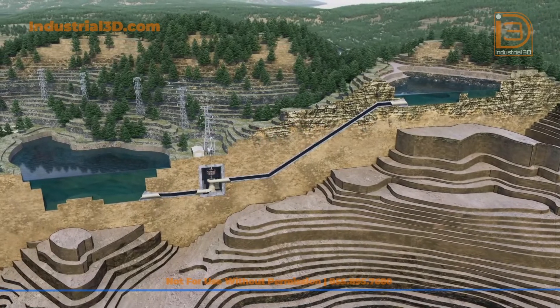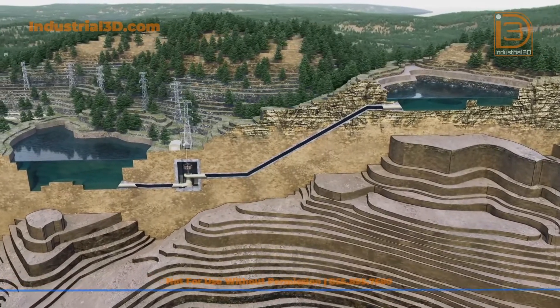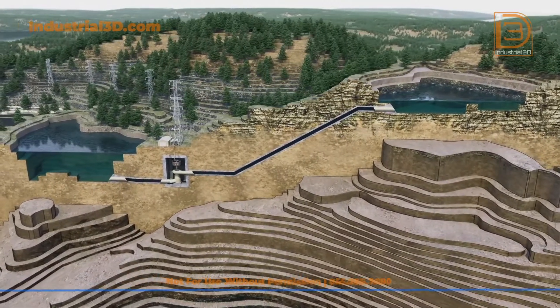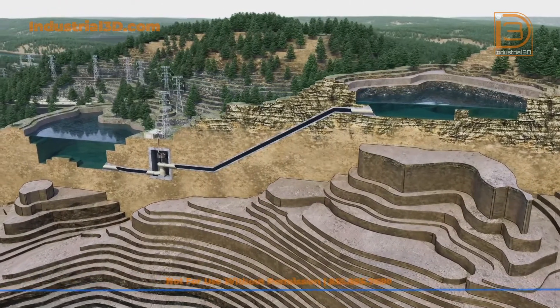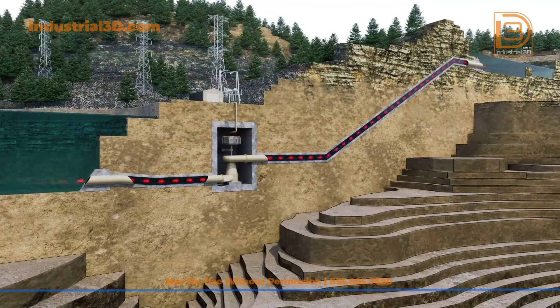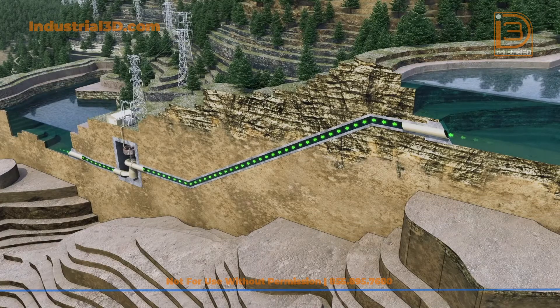The backbone of America's energy storage is pumped storage hydroelectric — it is 94% of actual energy storage. Pumped hydroelectric stores 10 to 20 hours of energy, compared with batteries, which store 1 to 4 hours. Pumped storage works by pumping water uphill to store electricity when excess electricity is available, and allowing it to flow downhill through a hydroelectric turbine to return electricity to the grid when it's needed.